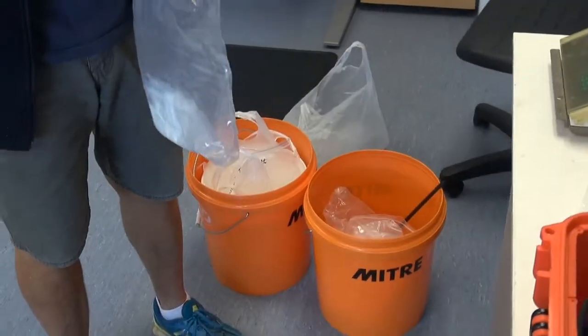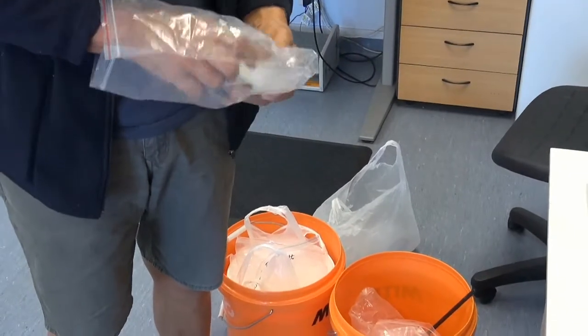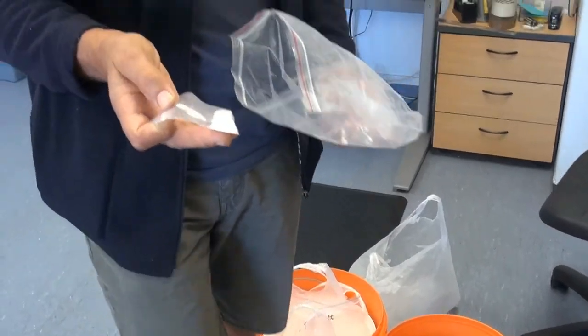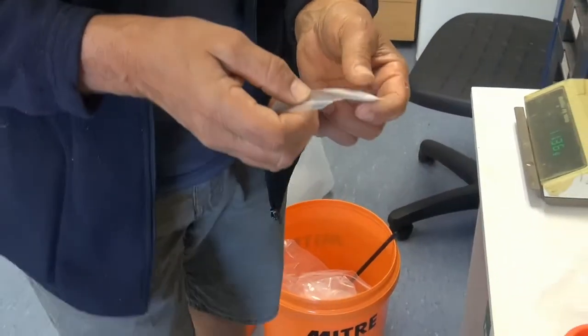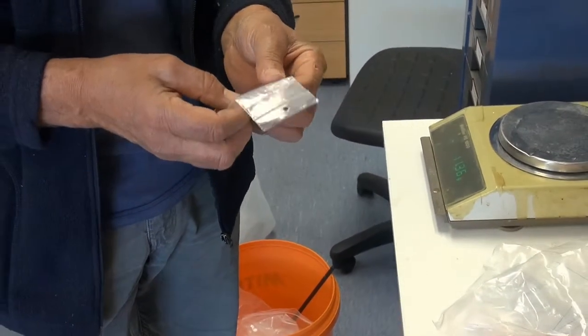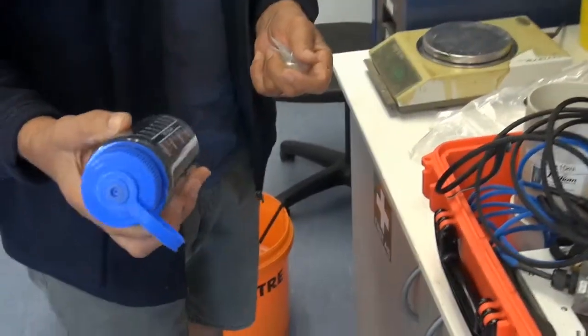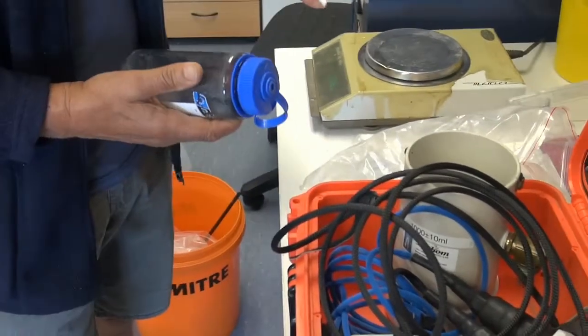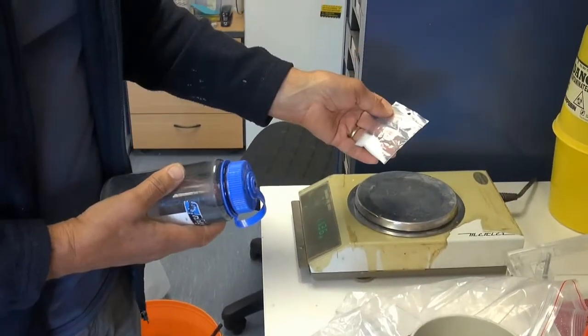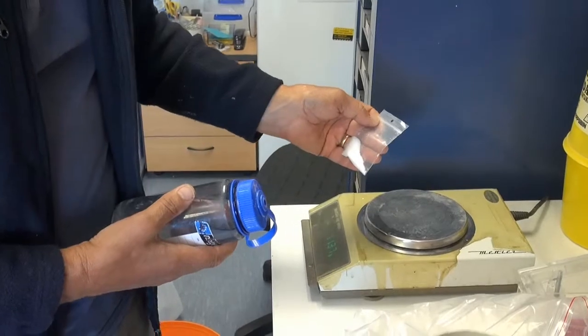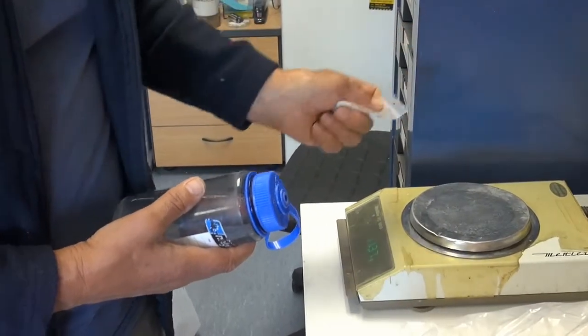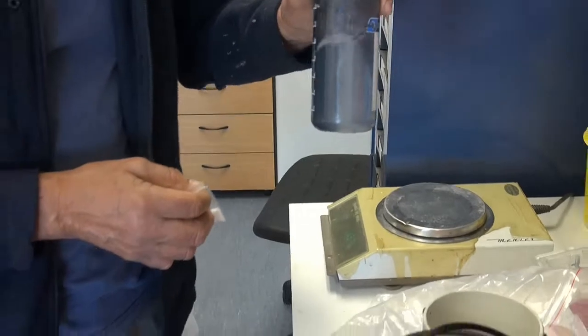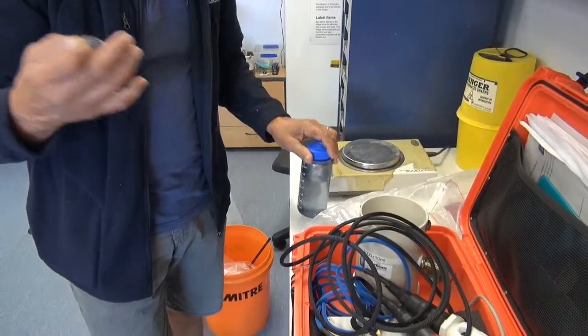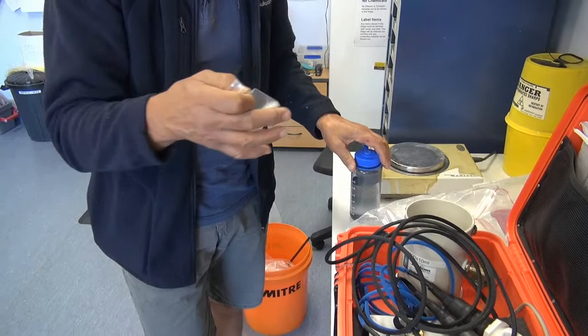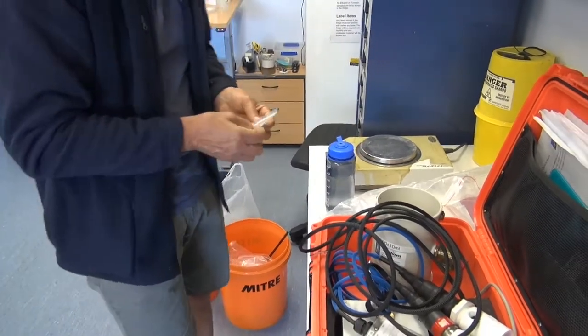The calibration solution that you want, you need 5 grams of salt in a litre solution for the calibration solution that you're going to use on site. So again, you just weigh the empty bag, zero the scales, and make up your 5 grams that way. I make the calibration solution up in the lab. Yep. But you do the calibration in the field because you've got to use the field water for that. Yep.